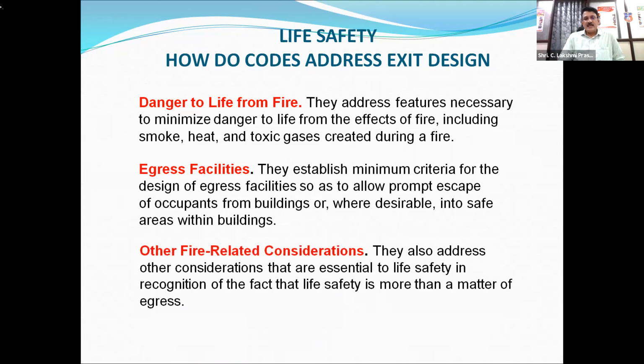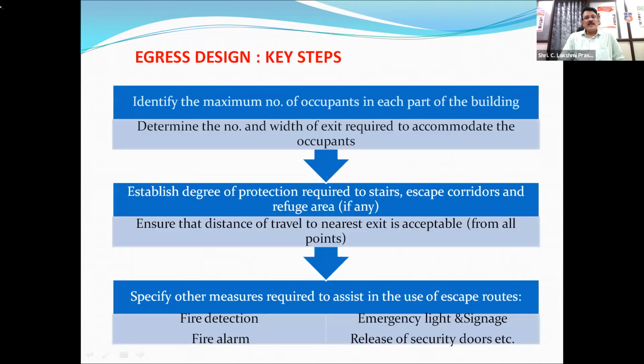Then other fire related considerations. These are the key concepts, the key steps in egress design. That is, we have to identify the maximum number of occupants in each part of the building. Then establish the degree of protection required for steps, stairs, escape corridors, and refuge areas. And specify other measures required to assist in the use of escape routes. So here NBC has given various tables for specifying the occupant load depending on the occupancy. For example, for a residential building, every person needs 12.5 square meters of area. So if you divide the area by 12.5, you will get the occupant load of a residential building.